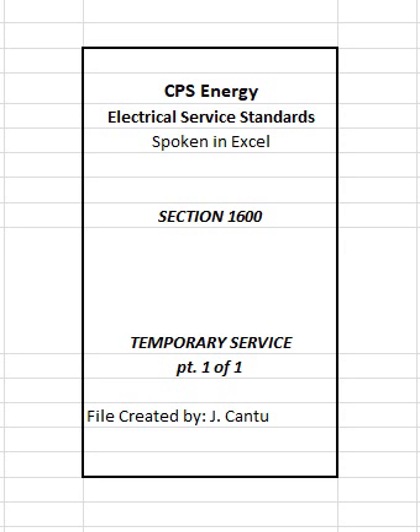1603 Temporary service laterals in URD areas. Service laterals furnished and installed by customer from CPS Energy pad mount transformers or secondary enclosures may supply customers service on temporary meter structures in URD areas. The standard method will be from pad mount transformers. Refer to definition of service lateral. Note: all applicable articles of Section 700 for URD systems will apply to temporary service installations in URD areas.